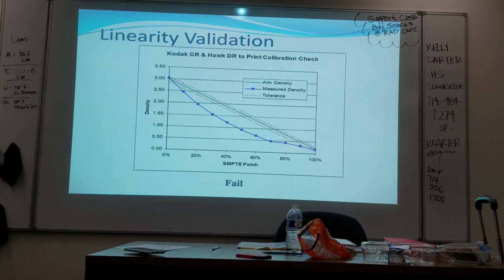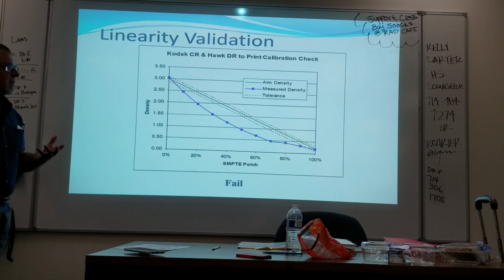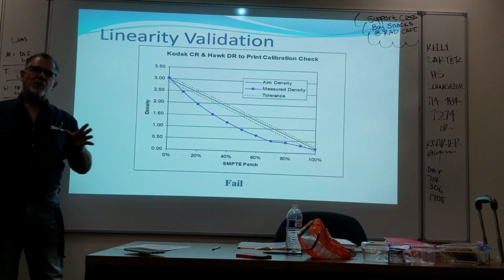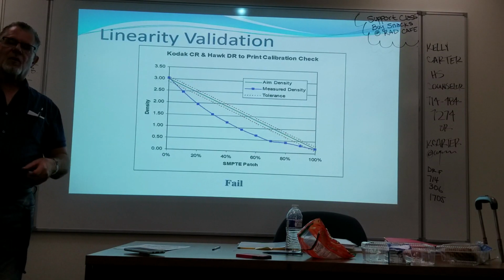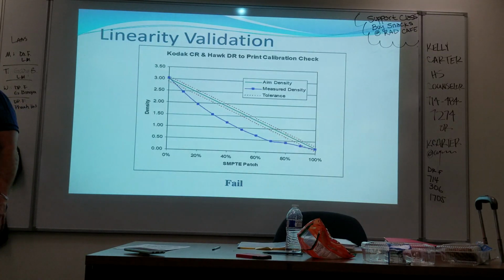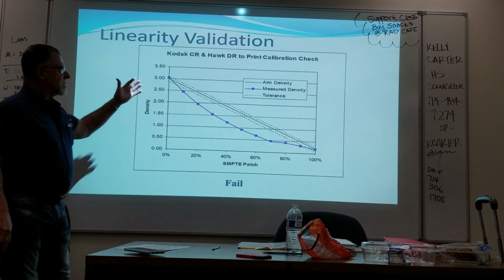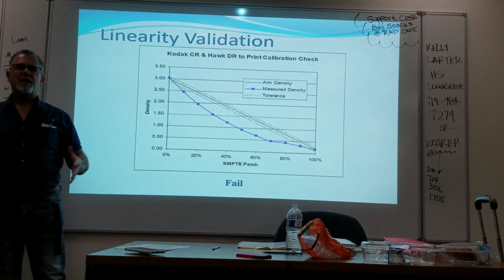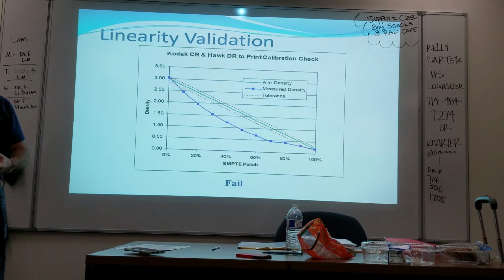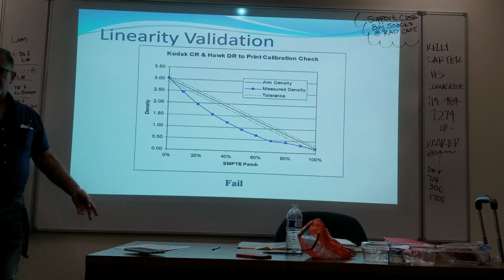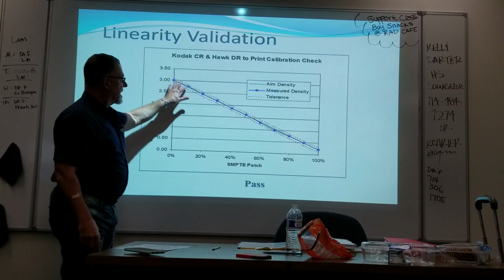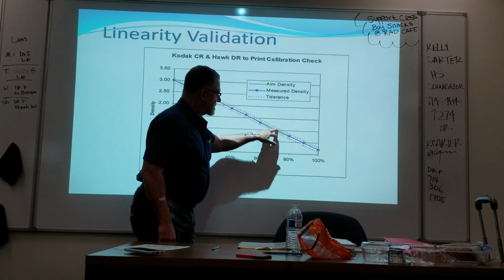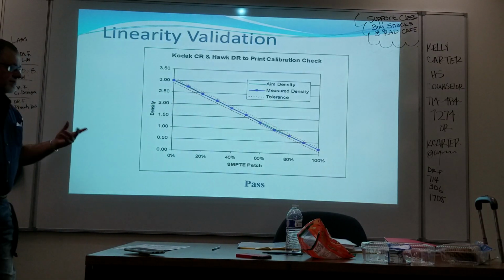The whole idea behind the digital image standard, DICOM, is that regardless of where you view an image, whether it's on a monitor or in the room or on a piece of film or on a physician's workstation, the contrast levels should appear the same. So you're not getting any distortion there. So obviously you'd have to recalibrate this, and with recalibration of the display, now you've got your measured densities well within the error bars, and it's good to go.